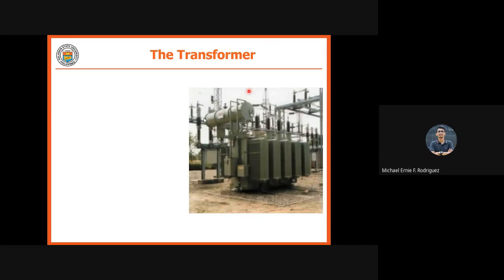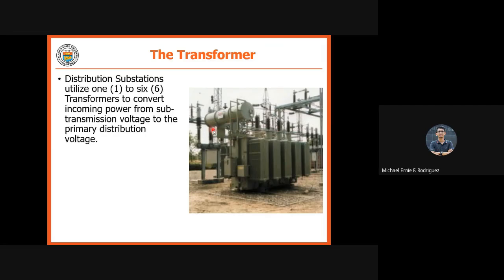So ito, tsura ng transformer natin on a distribution substation. Malaki yan. Depende kung ilang MVA. Pag mas malaking MVA, syempre, mas malaki yung transformer. So, distribution substations utilize 1 to 6 transformers to convert incoming power from substation sub-transmission voltage to the primary distribution voltage.